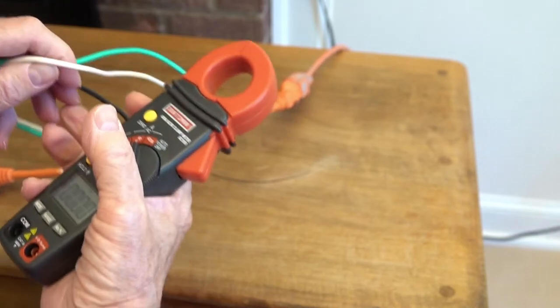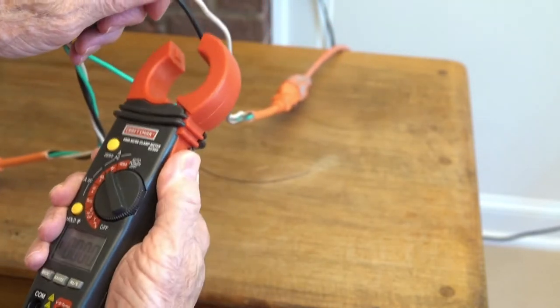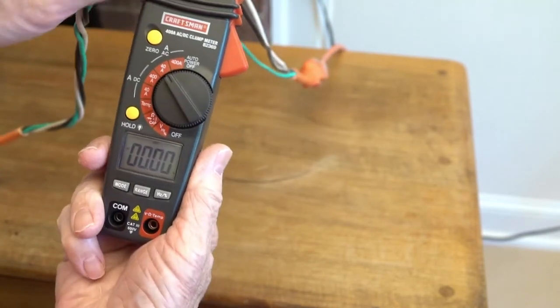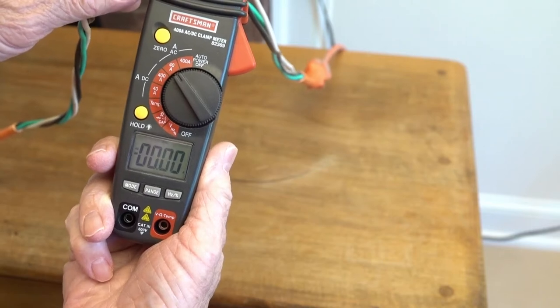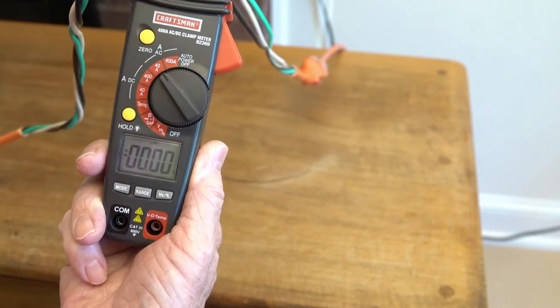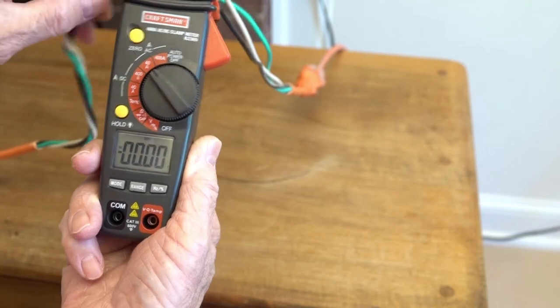Now, this is what happens if you clamp around both of them at the same time. You basically get zero. That's because the current is going in one way and come back out the other. They neutralize each other.